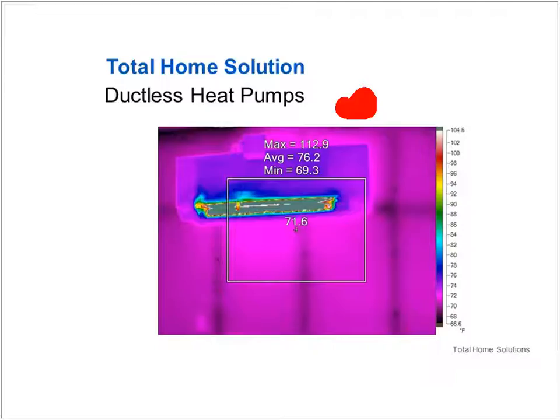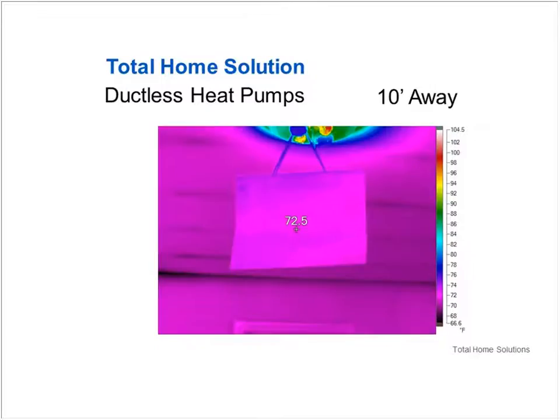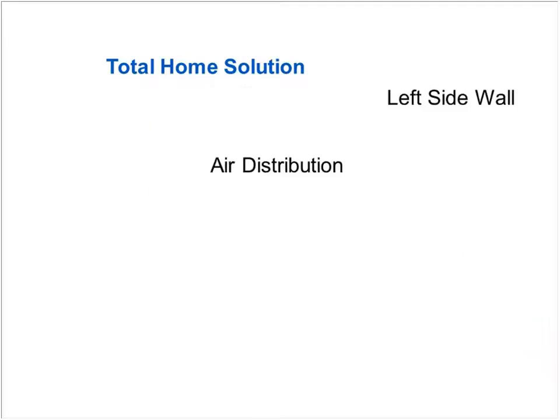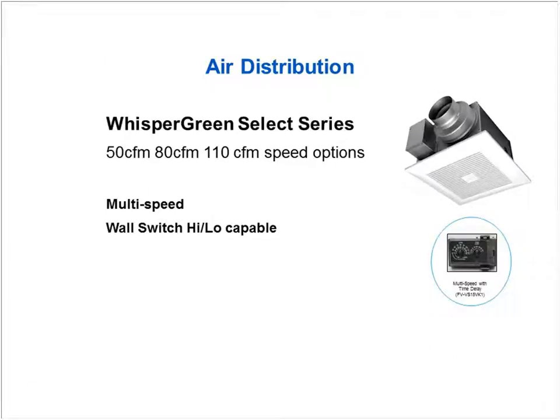So what happens is they're taking basically that 100-degree air, because by the time it gets up there and diffuses, the temperature's going down. The temperature's dropping as soon as that leaves that room. So that air is somewhat diffused in temperature, but it's still 100 degrees, and then they move that across that wall so that air is now moving into the other room. So that's an inexpensive way to move it. Now this particular fan runs that 30 CFM at about 2.5 watts of energy. So literally it's invisible to the occupant, and it just rolls that stuff across.